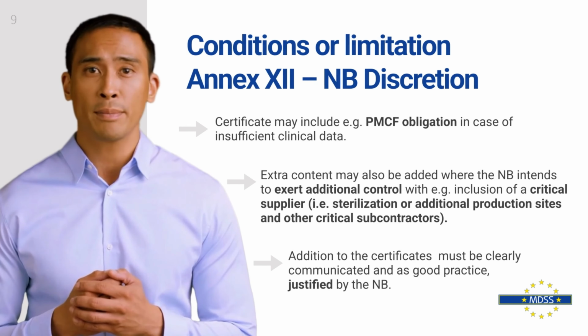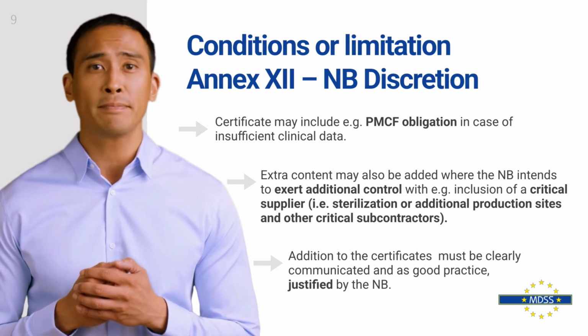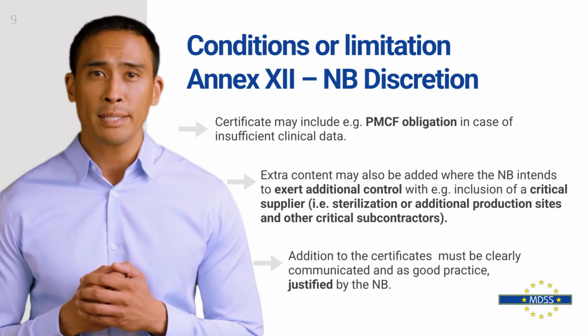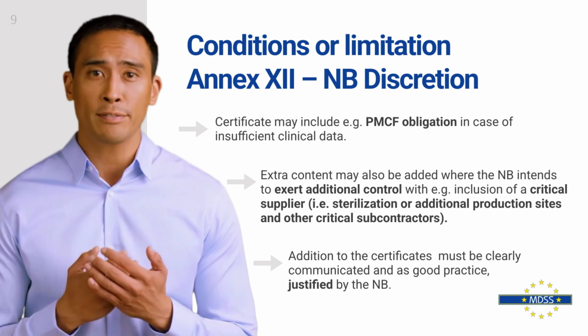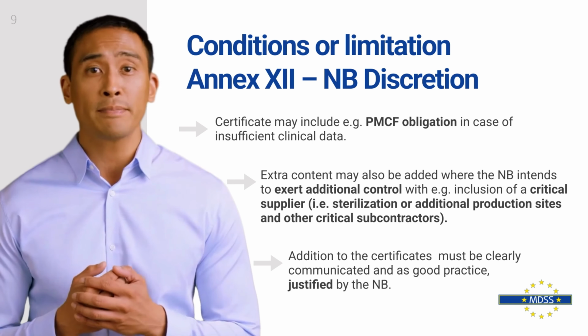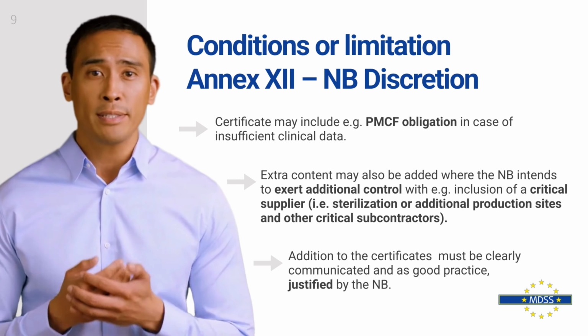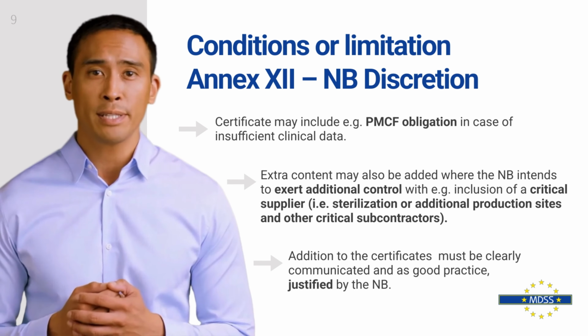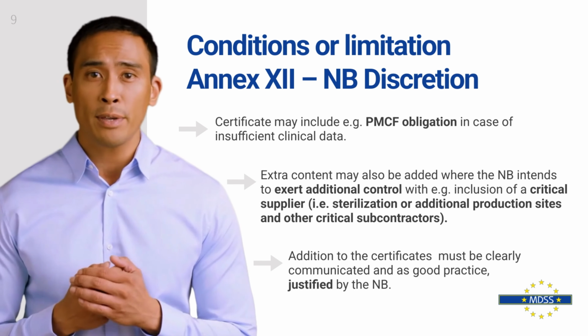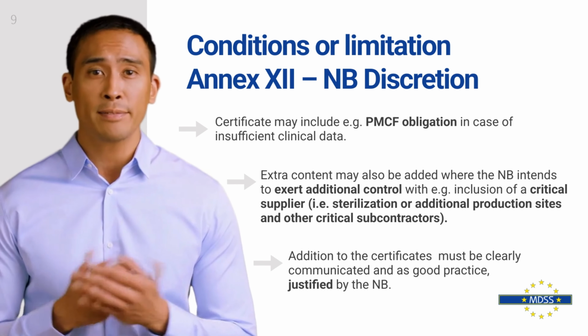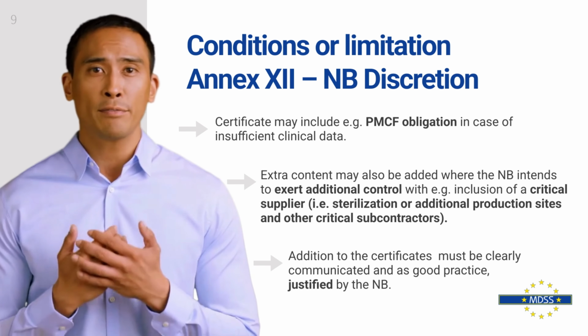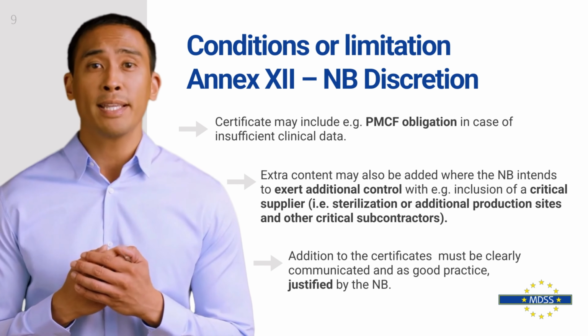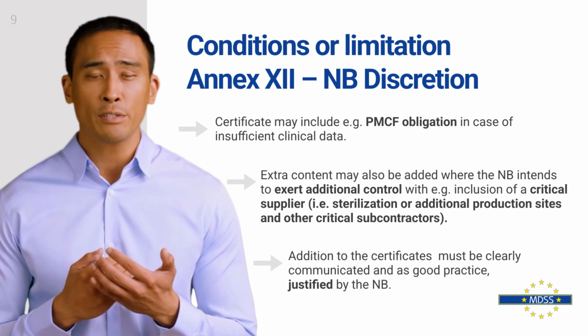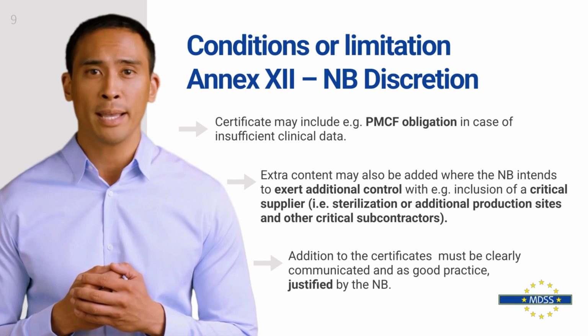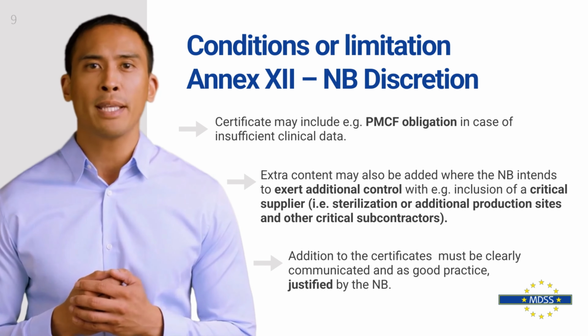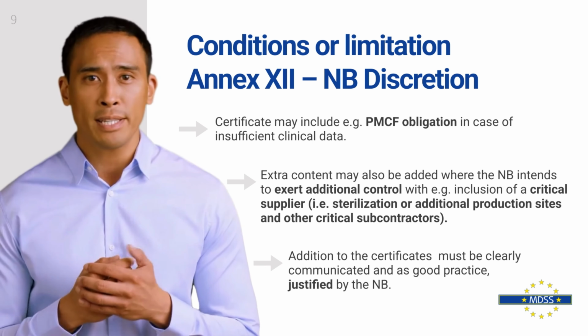Understanding the role of conditions or limitations and other certificate elements. Let's now take a closer look at how conditions and specific listings on the certificate may also define what constitutes a substantial change. Conditions may extend the certificate content. For instance, if the notified body determines that clinical data is insufficient, it may require post-market clinical follow-up activities. In such cases, the post-market clinical follow-up requirements may be explicitly listed on the certificate. A substantial change to the post-market clinical follow-up plan would therefore require the manufacturer to inform the notified body, as these would be considered substantial.